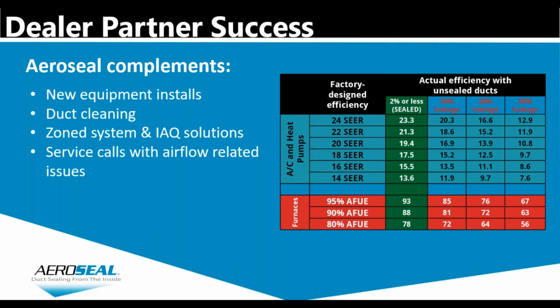We know that leaky ducts are going to pull in a lot of junk, and that junk is going to settle. It's just the effect of low airflow. By the way, on the return side, low airflow, where a lot of that dust settles, is going to be caused by leaks. So sealing on the return side and closing that up is definitely going to help with that. That clean and seal approach makes for a nice bundle that gives a good full day revenue and profit opportunity as well.